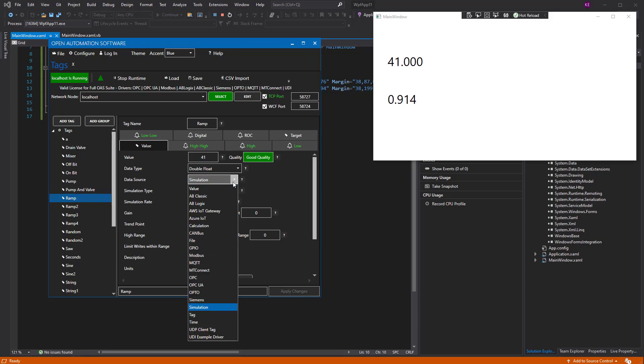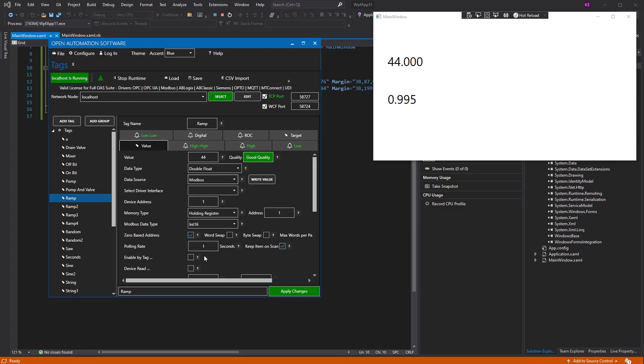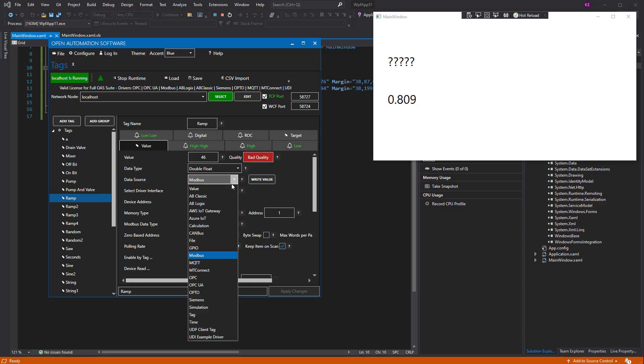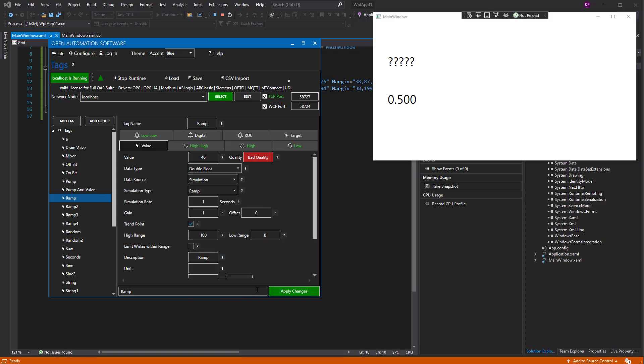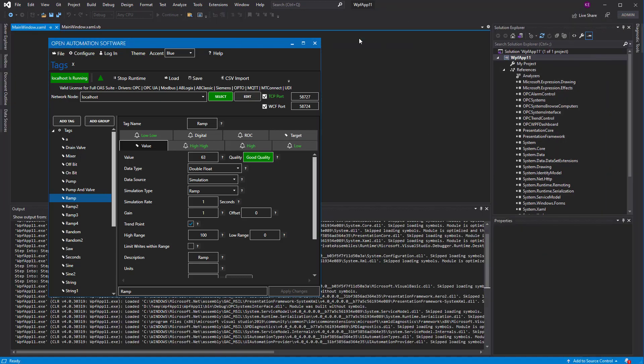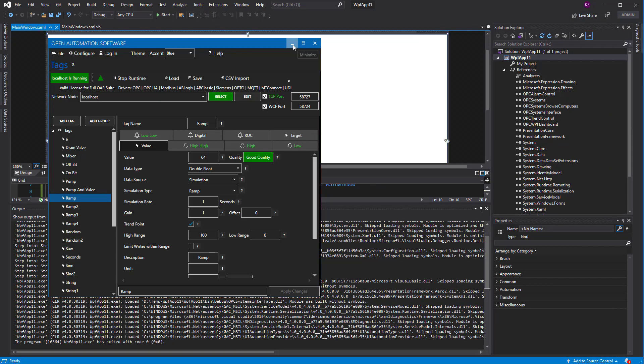And if we just change its data source to something that's, say, invalid, just say to a Modbus driver that doesn't exist, we see the data quality of that point goes to bad. So now, what the objective is, is we are going to add a hot backup feature to switch to another node when that data quality goes to bad. So let's exit the debug mode.